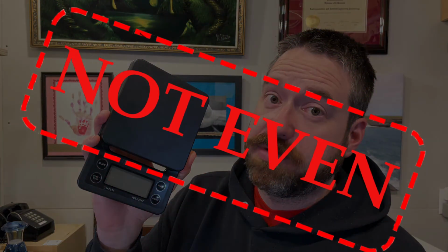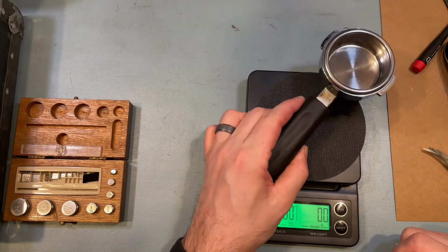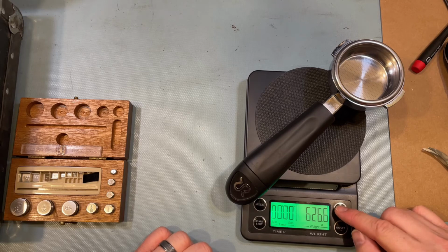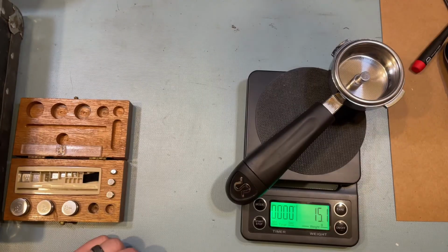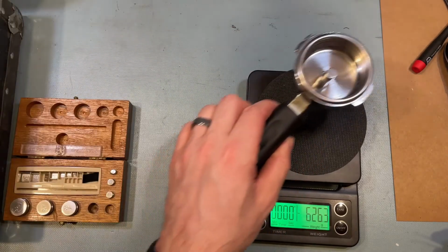We have carried out the most applicable of the 17 odd tests that would need to be carried out on a scale like this in order for it to be verified in the field. Now the question remains, could it be legal for trade? If a scale is not legal for trade, it can be as accurate or inaccurate as you are willing to pay for. This scale has 0.1 gram graduation.